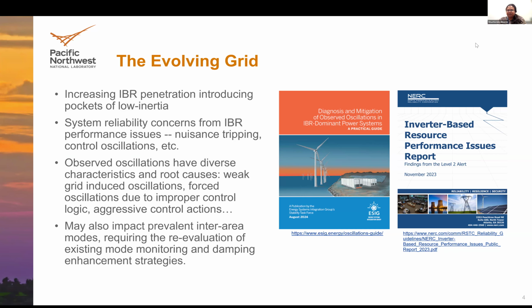And especially if the frequency of these oscillations is close to the electromechanical range, between 0.1 to 1 hertz, then sometimes these oscillations spread throughout the system, creating wide area reliability issues. And improper control parameter tuning is also introducing some of these oscillations. Some aggressive control actions, such as having gain values or time constants too aggressive, can also lead to oscillations. And that is not an IBR specific issue. If we have improperly set or too aggressive control actions for synchronous generators, then they have in the past introduced oscillations in the system as well.